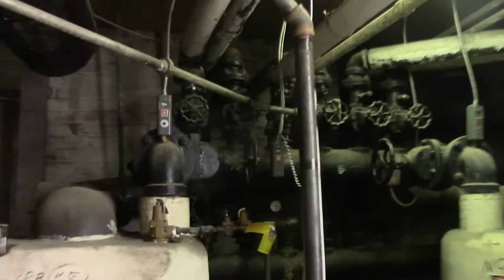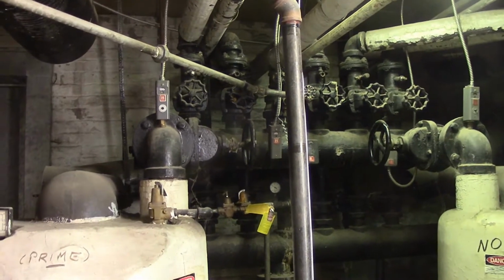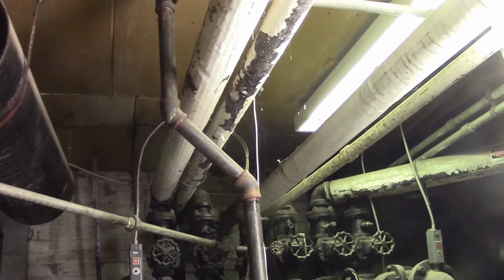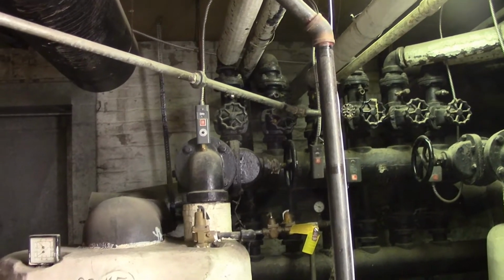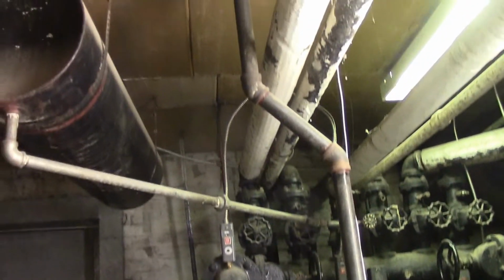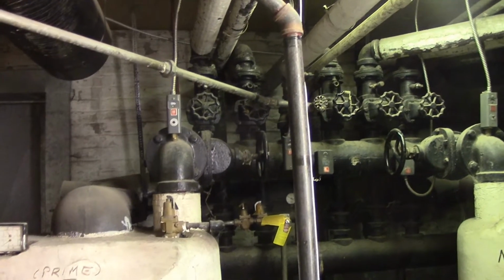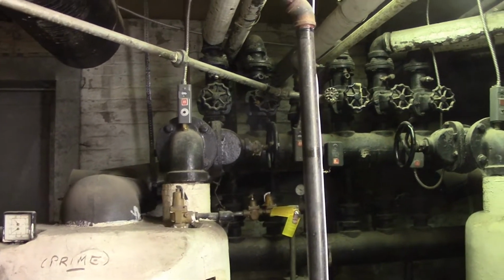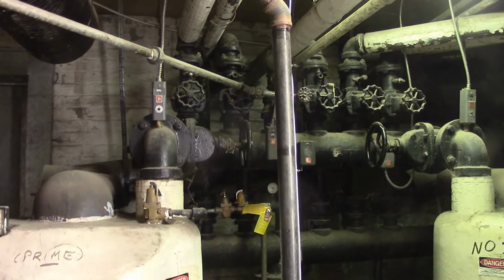There's also additional interlocks located on either side of the manifold, so there's a fair bit of security that's been wired into this thing. And it's all been converted to 24 volts, like I said. It makes more sense to allow, if there is a short or failure in this old wiring, 24 volts at a negligible amount of milliamps, as opposed to 120 volts and, I don't know, 15 amps.